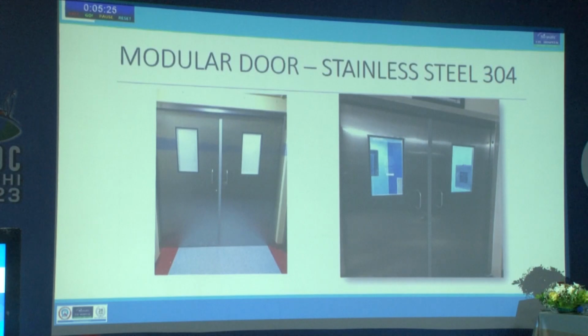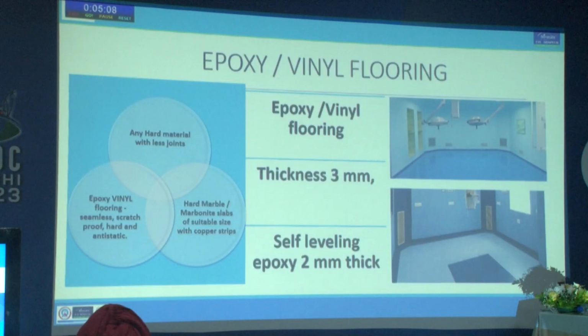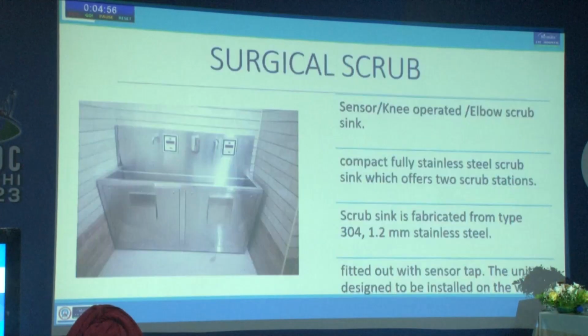Then for the modular door, you can use stainless steel, but ensure it is medical grade, because we'll be using a lot of chemicals. So most often we see over a period of time there is a lot of corrosion as well as dents in the steel. Ensure the vendor uses good quality steel. If at all, bargain for the best. So for the flooring, you can use epoxy or vinyl flooring. Ensure that the thickness is 3 mm and it is properly leveled, because epoxy generally over a period of 5 or 6 years can get damaged.